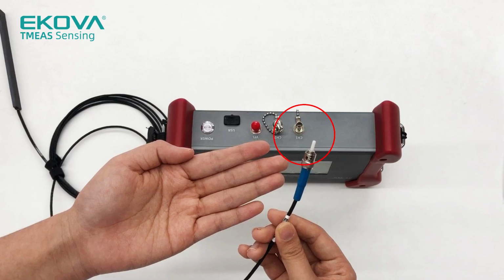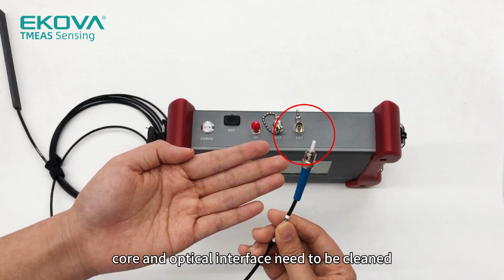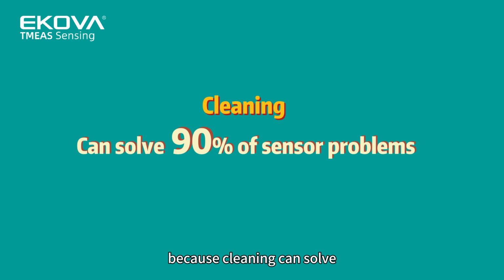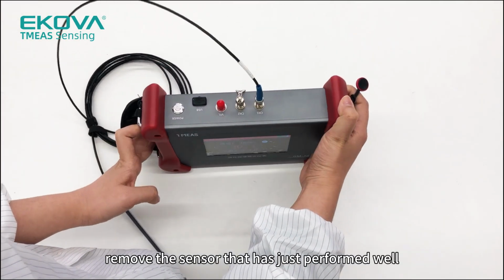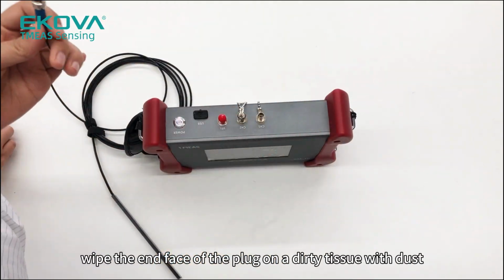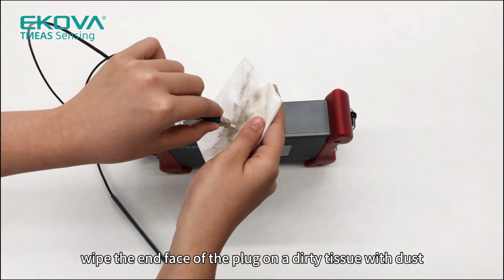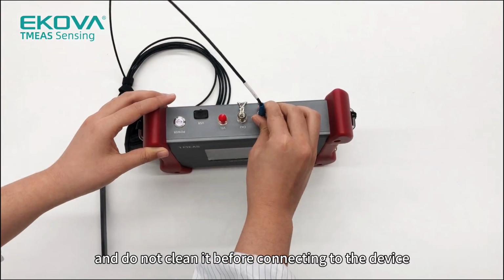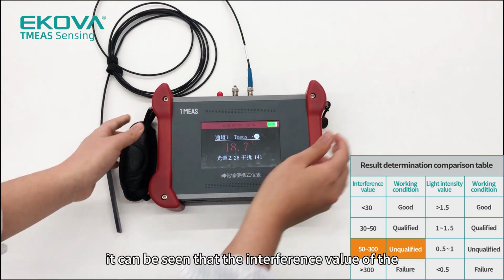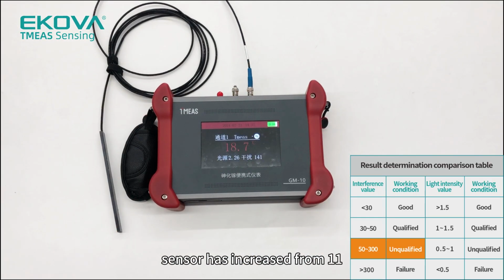A final note: why has it been emphasized earlier that before the sensor is connected to the device, both the connector core and optical interface need to be cleaned? Because cleaning can solve 90% of the sensor's problems. Let me show you. Remove the sensor that has just performed well, wipe the end face of the plug on the dirty tissue with dust, and do not clean it before connecting to the device. It can be seen that the interference value of the sensor has increased from 11 just now to about 145, and the temperature measurement performance has deteriorated.